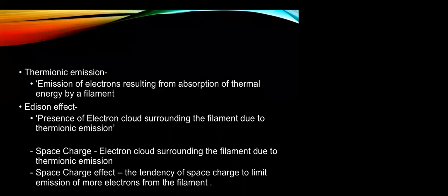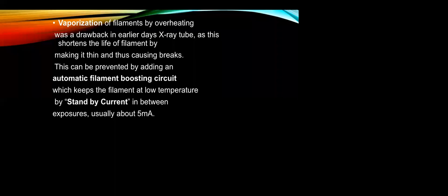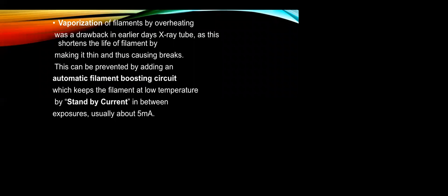An important consideration is vaporization of the filament. Because the filament is repeatedly heated, it may lead to overheating, which was a drawback in earlier X-ray tube decades — it shortened the life of the filament by making it thin and causing it to break. This can now be prevented by adding an automatic filament boosting circuit, which keeps the filament at low temperature using a standby current of about 5 mA between exposures, so that in between exposures the filament does not get overheated.